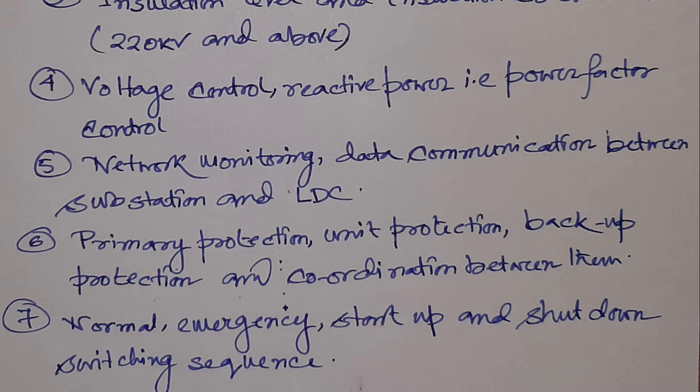Then comes the operating sequence — the normal operating sequence, emergency operating conditions, and what will be the operating conditions during startup and shutdown. For example, if a switchboard has two incomers and one bus coupler, the general tendency is that the bus coupler will be in open condition and the two incomers will be in closed condition, each taking 50% of the total switchboard load. This kind of operating philosophy — which transformer will be working, what will be standby, which breakers will be closed or open — all these things need to be considered during substation design.